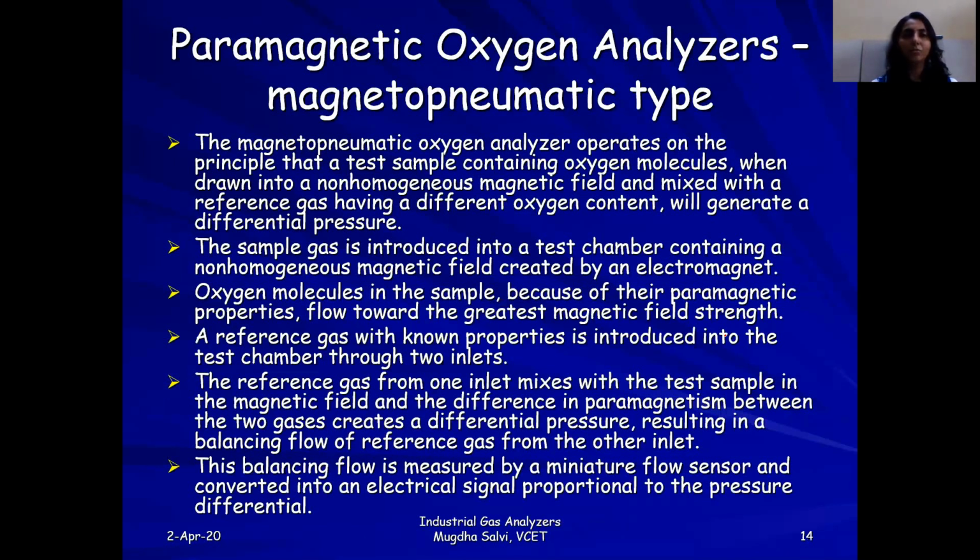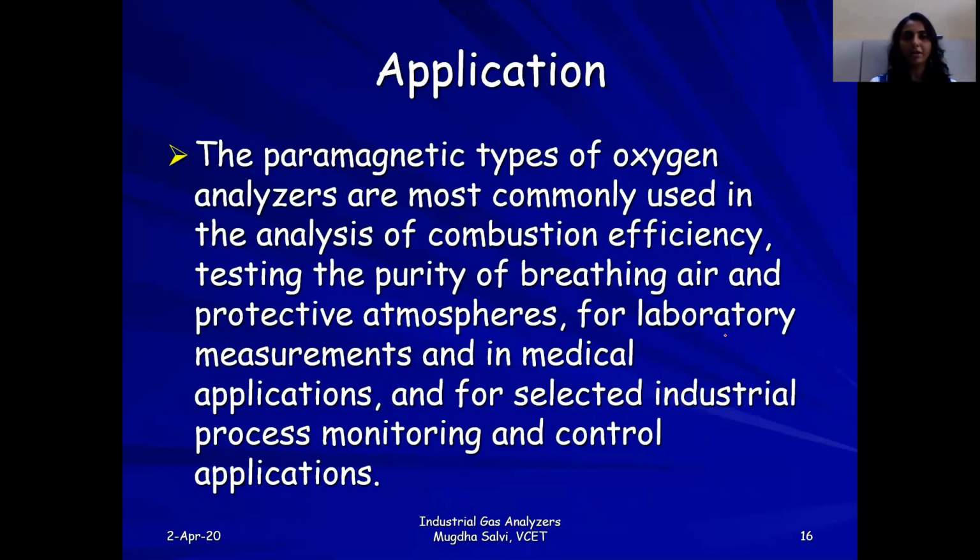This is the magneto-pneumatic type. The magneto-pneumatic type oxygen analyzer operates on the principle that a test sample containing oxygen molecules, when drawn into a non-homogeneous magnetic field and mixed with a reference gas having a different oxygen content, will generate a differential pressure. The sample gas is introduced into the test chamber. I am not able to locate a diagram for this, so I have not included it. You can neglect that one.